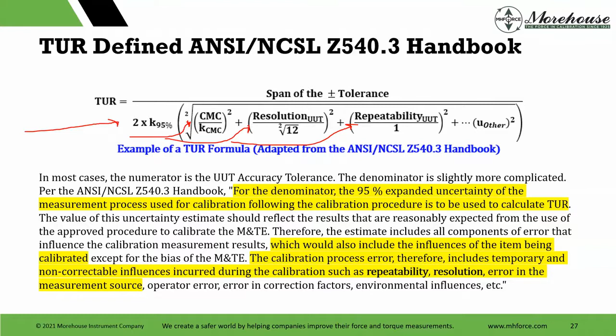So this is a 10,000 pound load cell. Really not much changing here. Just two pieces of equipment, primary standard versus secondary standard. There's a whole slew of things with timing and everything else. Lot of error over here, right? That's probably not captured in that calibration and measurement capability of 0.05. But besides that, let's go with what people may claim.